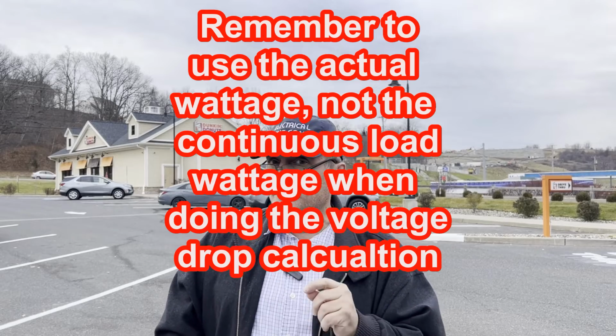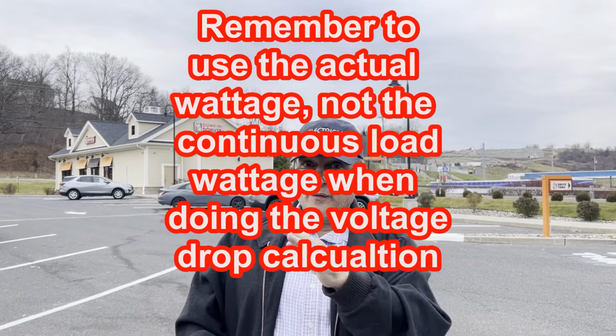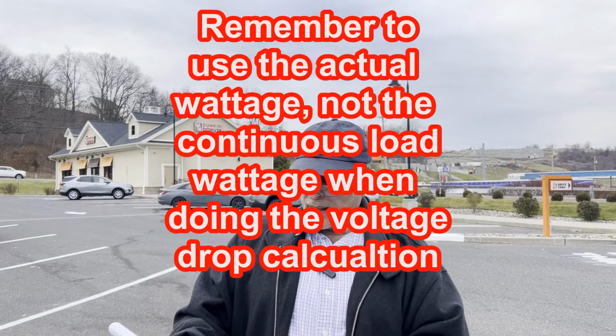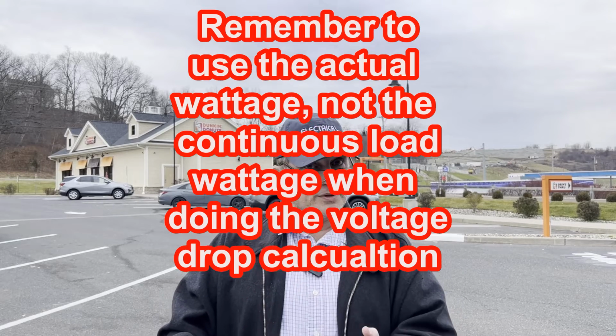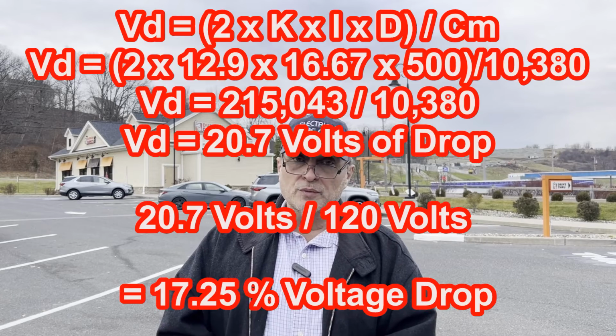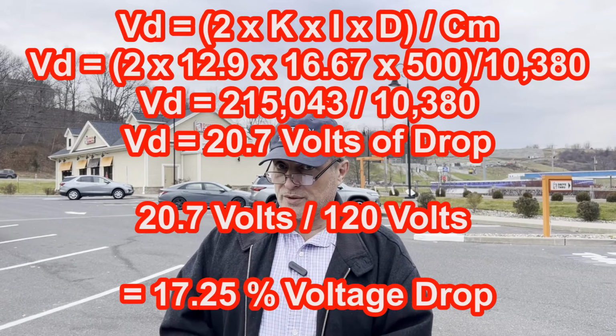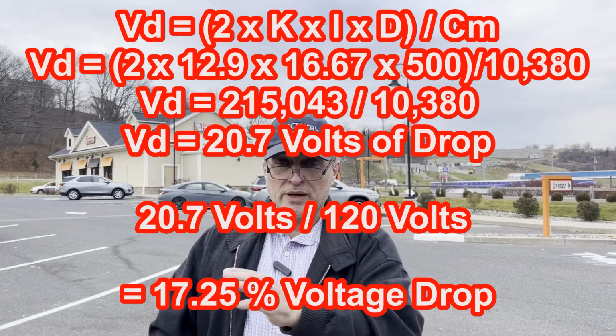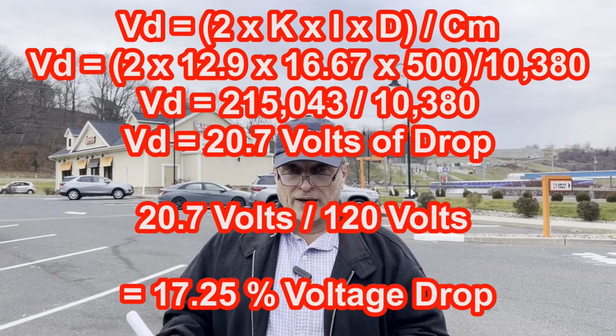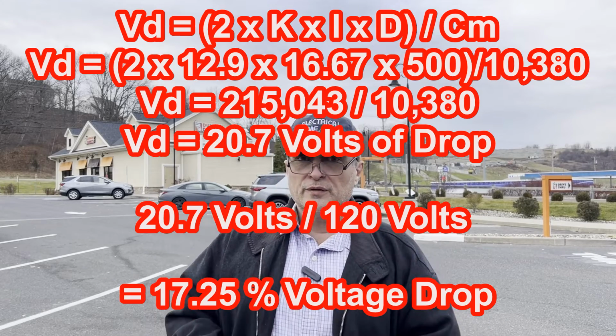So when we take that formula, and again, that's VD is equal to the product of 2 times K times I times D, and you divide that whole thing by CM, and when we plug in the numbers into that, we get to an actual voltage drop of 20.7 volts. And you're going to see all of that on the screen here. So I know I'm going fast, but this is a review question for my class.